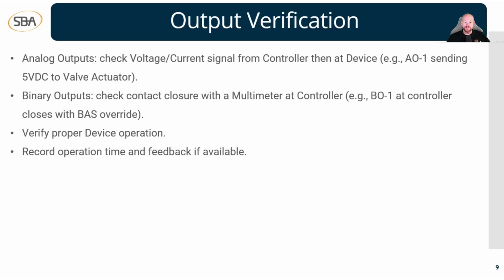So for this one, we need to check and make sure that our contacts are closing if we're sending the signal out. We can check this with a multimeter. We can check this with the continuity tone beeper on our meter as well. But we would check this contact closure with a multimeter at the controller. So an example here would be binary output 1 at the controller closes with a BAS override. So we override a fan start/stop, for instance. We can check the contact on the controller, that output contact, and make sure that it did close when we overrode it on.